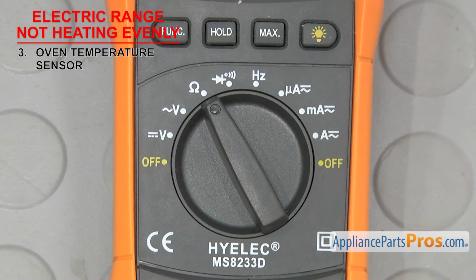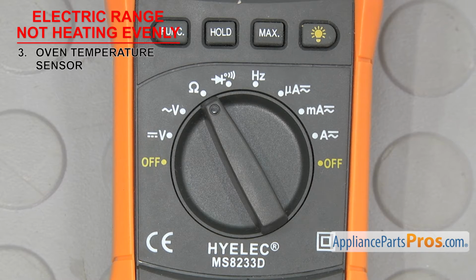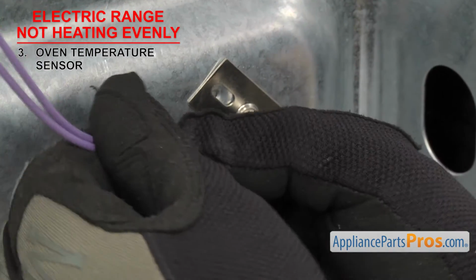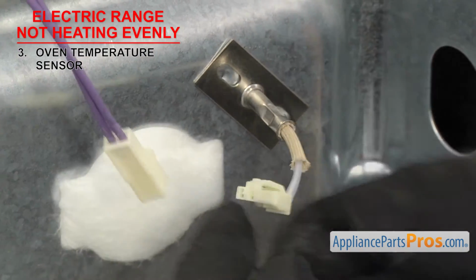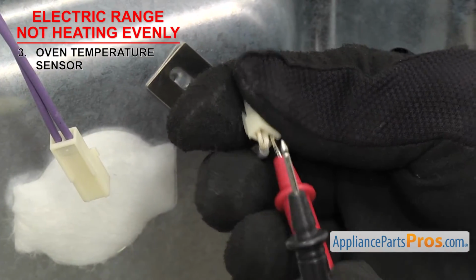So set your meter to ohms. Our meter automatically detects whatever ohms are coming in, but you may need to set your meter to read the proper ohm level. Once you have access to the sensor, remove the wires and touch a test probe to each terminal.